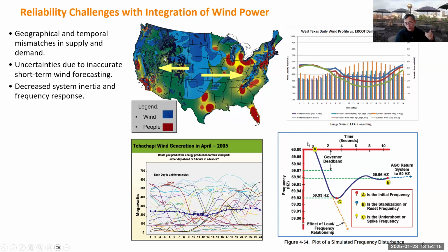If the inertia is very small, the frequency will quickly drop to a very low value, which can trigger frequency protection. The governor of the generator only becomes active after a couple of seconds, because each governor has some dead band, taking 1 or 2 seconds to start bringing the frequency back. Then we can utilize AGC, which comes maybe 10 seconds later. So even with a very strong governor and strong automatic generation control, you still cannot guarantee the frequency won't decrease to a very low value. That only depends on inertia.